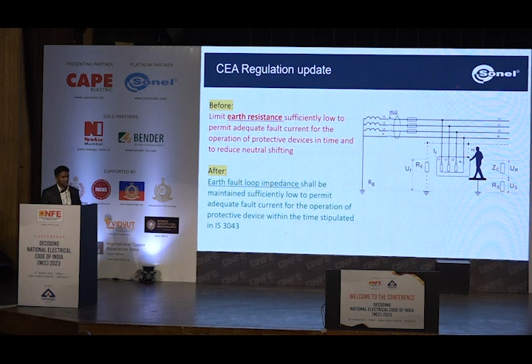We measure the earth resistance sufficiently low, keep it at 0.5 ohm, 1 ohm - but that's not sufficient. You need to know the entire fault loop value. We calculate the impedance of the total circuit, and then you can correlate it with your standard document, which says what is the tripping time or characteristics as per the MCB.